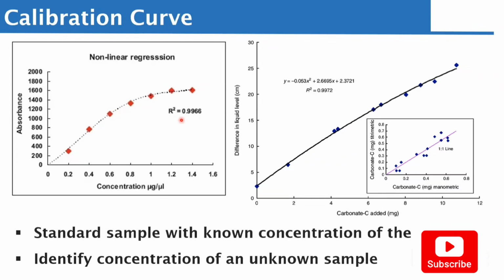One of the things you're going to do is to redo the calibration. I'm saying it's not in all cases. However, we repeat calibration if we find out, number one, maybe the lot number of the calibration plasma or calibration sample already in the analyzer is different from the current lot. So what you then need to do, in order to make sure that the current control sample is not running with the old calibration lot number, is redo it with the current lot number.